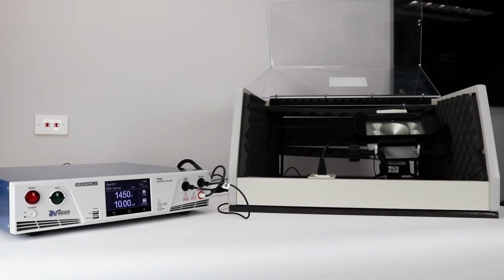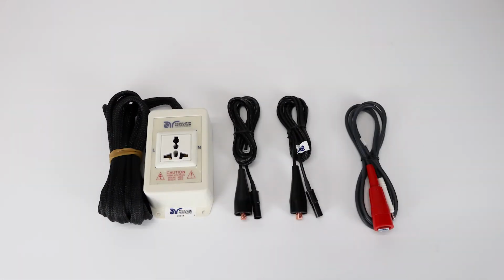Finally, we're going to show you how to connect the HypotULTRA to a DUT and run the test sequence. You're going to need the following accessories: the red high voltage lead and 2 black clip leads. You can also use the universal style adapter box instead of the clip leads. An instrument with scanner channels also comes with 100 feet of high voltage wire and high voltage terminal connectors.